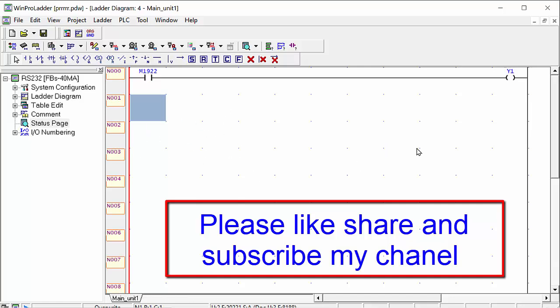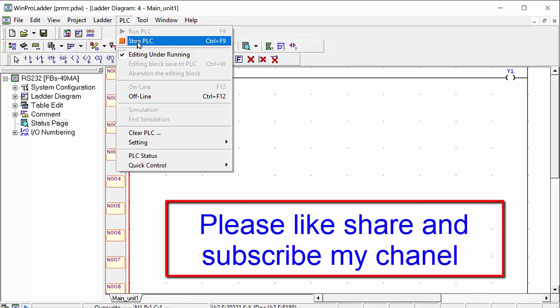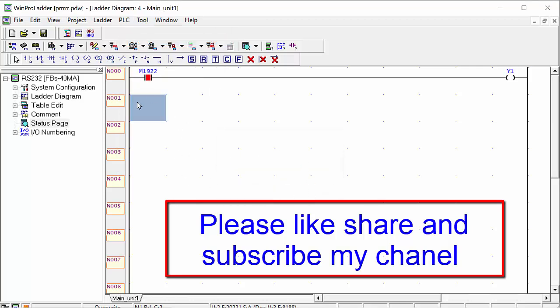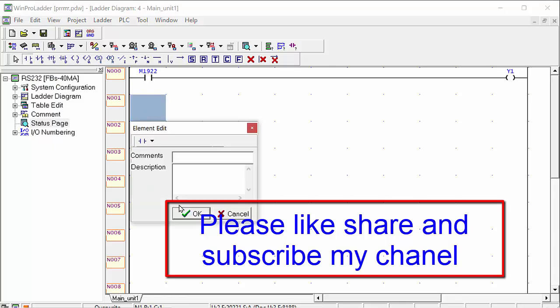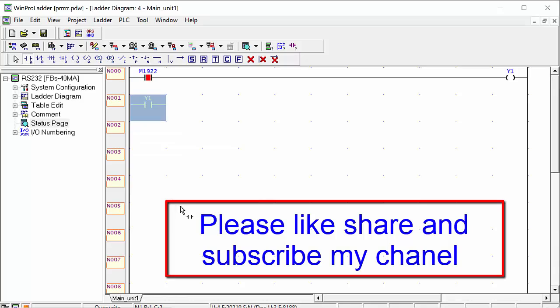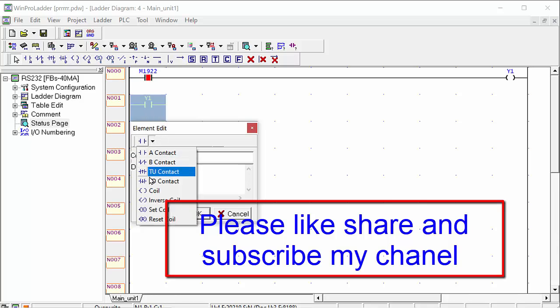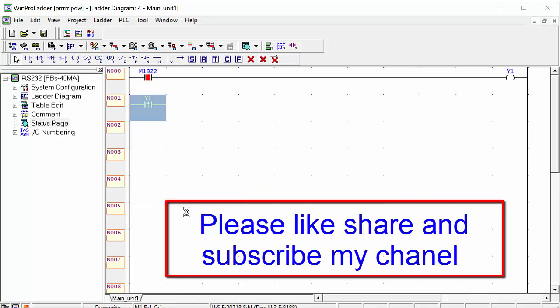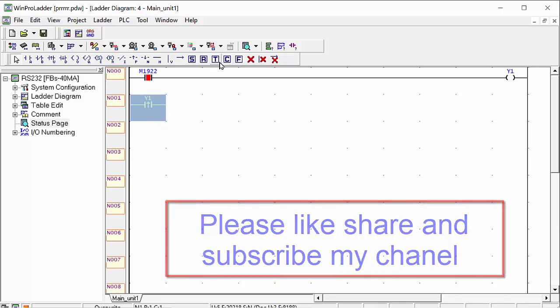If you like to make it, let's see how. Stop the PLC, and simply this pulse which is coming at Y1, you can use for the increment command. Because it cannot be used directly, you have to design the logic. First design the logic, use the input signal of Y1 and mix in the increment. You can also use this as a rising edge contact, which gives a single pulse, and here you can make it for increment.